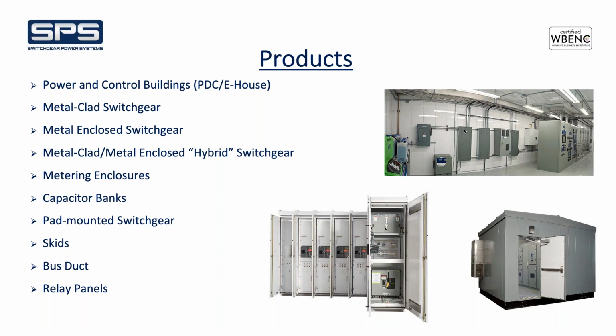Metal clad, metal enclosed hybrid switchgear is what we refer to as gear that has a combination of switches and circuit breakers. So props to Michael. This picture right here was actually a project of Michael's where we integrated a main breaker with switch fuse for the feeders. This customer didn't place the value on circuit breaker protection on the feeders, so they saved themselves some money and went with fuses.